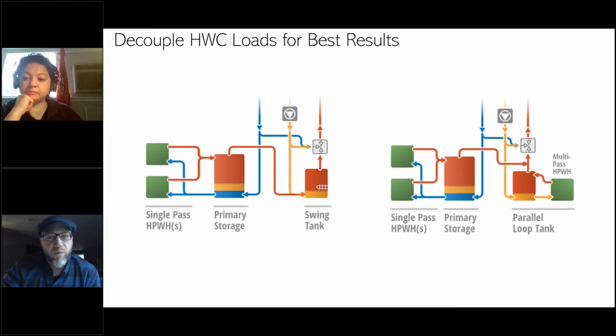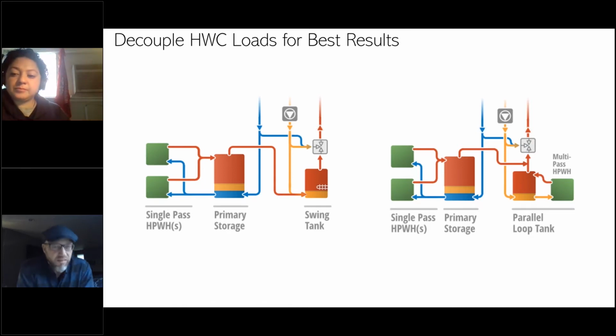I'll show you a graph in a minute on why, but I've shown two schematics here. One is the swing tank schematic over to the left, a gang of heat pumps working on one batch of storage. That storage is stratified, so we use single pass heat pumps, and we send the water to the top. Then there's a swing tank, used primarily to deal with the hot water circulation or the temperature maintenance load. So there's two ways to do that. You can do it with a swing tank. There's also a parallel loop tank. When the loads get too big and essentially overwhelm your primary plant, then you want to consider a dedicated heat pump for your recirculation.